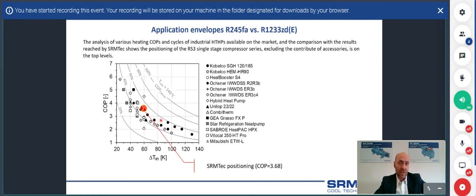If we consider the 60 K of temperature lift, the results we have reached position our results at the top, higher levels. Even if we are not considering the pumps' consumption of the system at this moment, because we are considering only the compressor, this shows that even if we were to consider the absorption of the pumps, the system is positioned in a very good way, as I mentioned before, in the higher levels of efficiency.